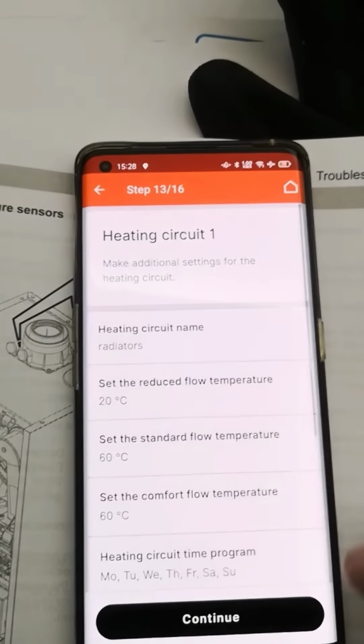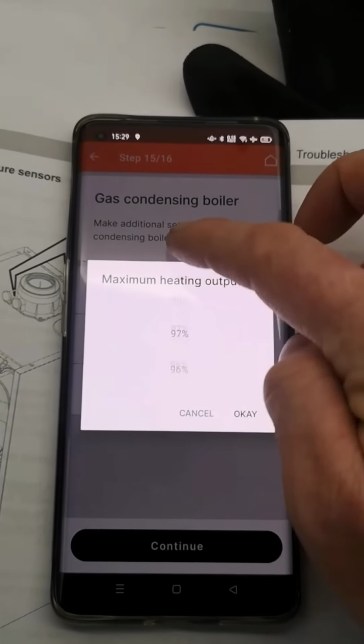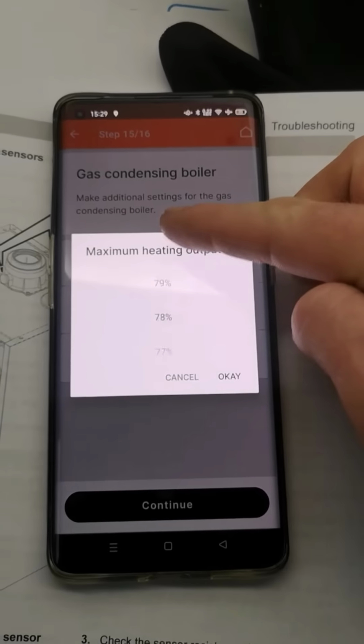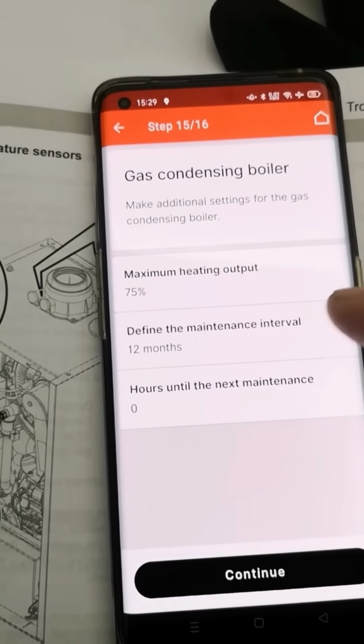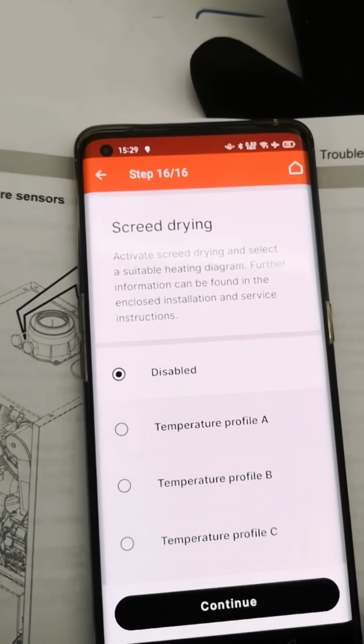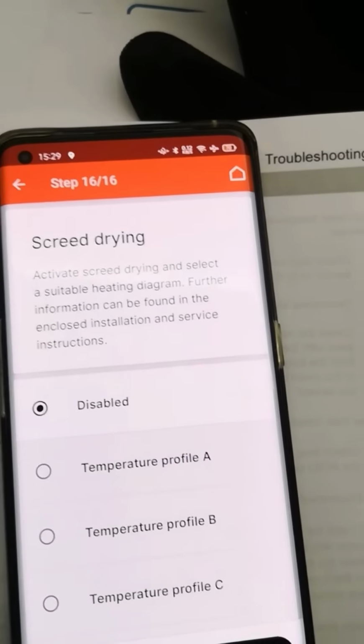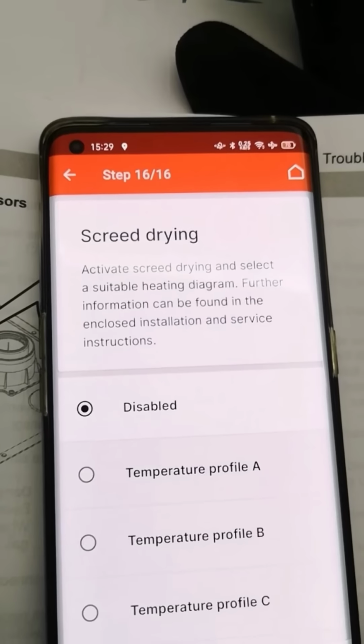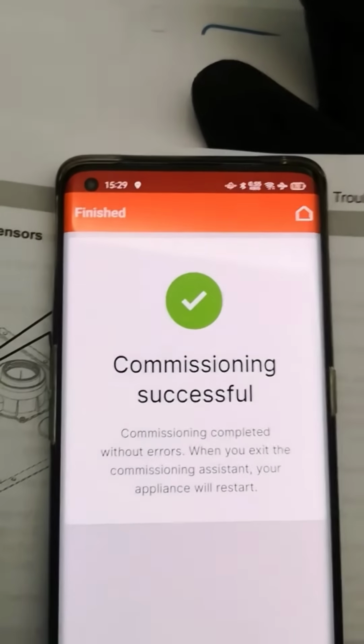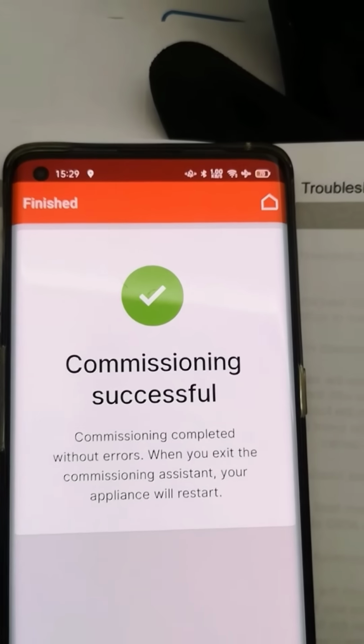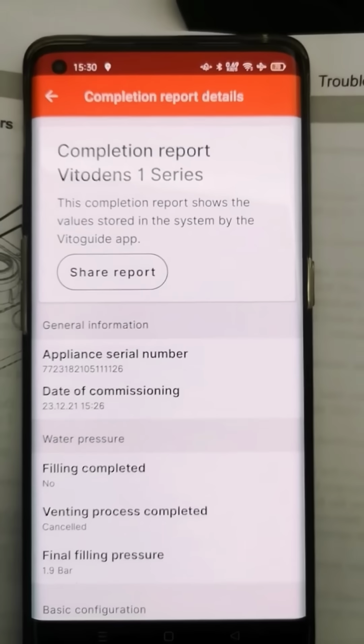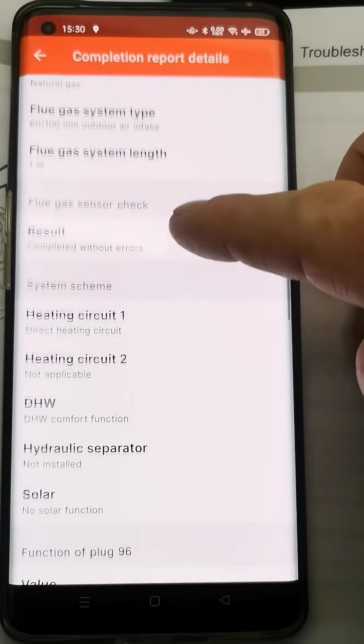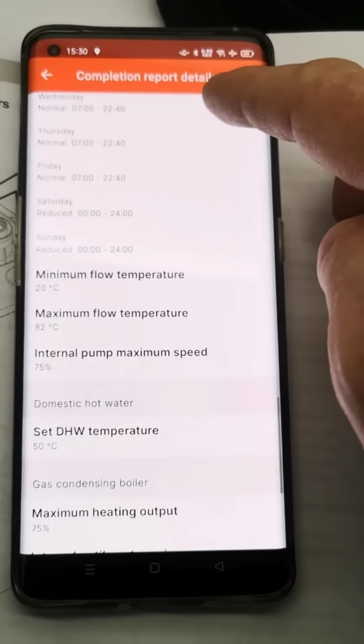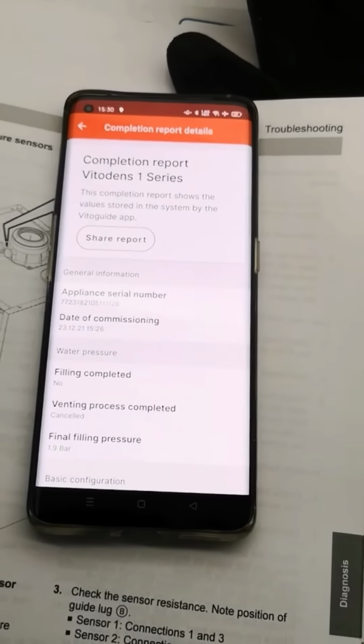To set at 50, and the customer can turn it up and down if they want then. Also, if we want to modulate the boiler down, we can change this. And we can also bring the reminder up for the annual service. If it's underfloor heating and fresh screed, it's also got the screed drying. And what's really good now is once you've done this, it'll actually give you a PDF file to send to the customer. So it'll tell us all the information that we've put in, and then this can be sent off to the customer. Nice little touch.